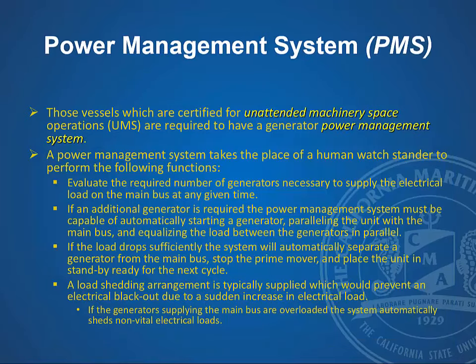You also have to have a power management system, and the Kongsberg diesel simulator has this, and that power management system will automatically put generators on the line and take them off the line without any human intervention and to maintain the capacity of the system. In other words, if your load on the system gets too high, it will automatically put a generator on, and when the load drops back down, it will take a generator off. And you're going to set priorities, which generators you want to be your primary and which is your secondary. All of these features are put into this, and we'll be talking much more about this in class.